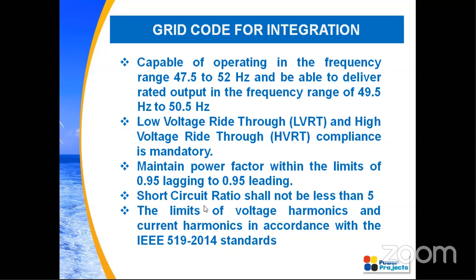The very important thing which denotes the stability of the system is the short circuit ratio, SCR as we usually call it. It should not be less than 5. Usually our wind plants and solar plants will have less short circuit contribution, so I will be dealing with this in detail. Let's see that in that particular slide. The limits of voltage harmonics and current harmonics should be in accordance with this standard. So this is just an outline. Let's see each point in detail.